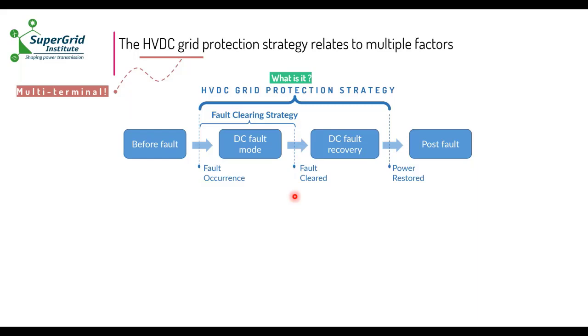So this will cause the system to lose voltage and power for some time. And we need to be fast to detect where the fault is. So in the first part, the fault clearing strategy will locate the fault and interrupt the fault current. And the protection also will take some role after the fault interruption to quickly recover the voltage and then put back the power through the DC network. So it goes until this post-fault power restoring step.